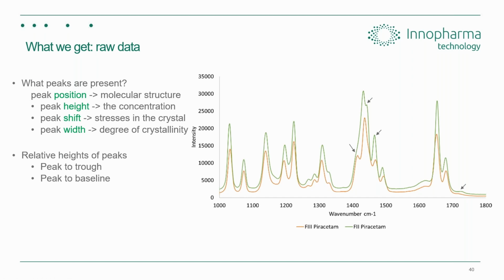So the baseline can be a measure of signal from the crystal itself, but it can also be a signal from the solution. So the baseline is one of the things that we sometimes have to remove, because it can be attributed to the background, any stray light that's present. And you saw earlier that the reaction is open to light from the laboratory, and our floodlights, for example, could even influence the experiment.